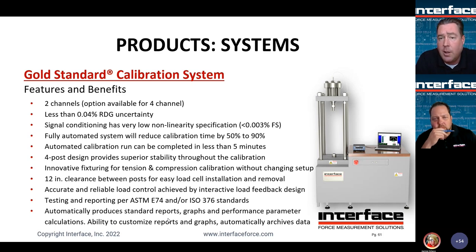These are very nice in that the hydraulic power unit is integrated into the frame itself. So you can see we have the piston on the left-hand side of the frame. The HPU lives on the right-hand side of the frame. And this functions directly with our E74 calibration software and is even more integrated in that it has its own control feedback. So not only can you enter in your calibration data from your reference standard load cell, this will actually control and automate the calibration process.